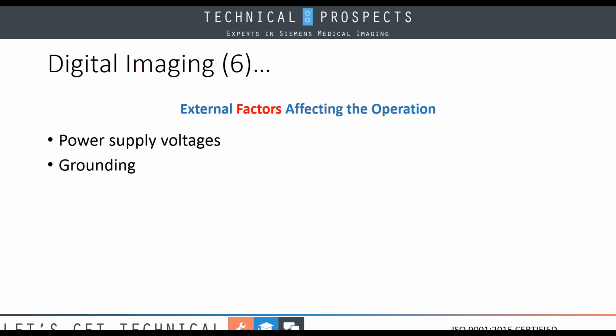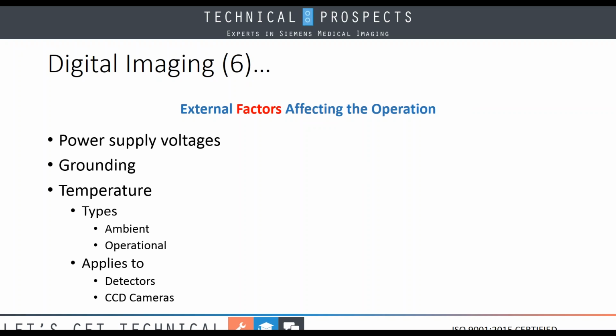to properly respond. Some other factors that will affect the operation, the biggest one is temperature. For those of us that have played with these digital detectors out there in the world, when you get a brand new one, it tells you to let it sit for 12 to 24 hours while it gets used to the ambient temperature. We all know that the technicians want us to get in there and just do it right away. We can't, because we have to allow it to get used to its environment. The other thing that some manufacturers are doing is holding off and forcing it to be at an operational temperature before it allows you to even do the calibration. So both of these temperatures are something that you need to be aware of and comply with in order to ensure that our detectors will give us the proper output.